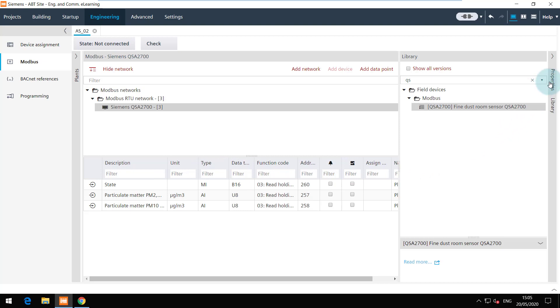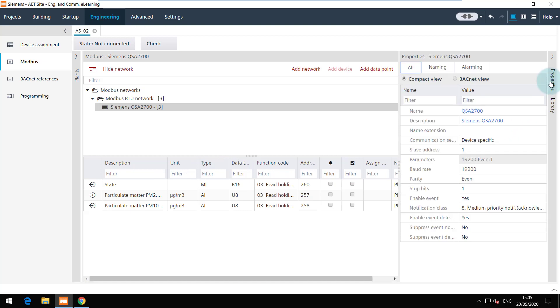In the properties of this device you can see that the communication settings are set to device specific which means it is not inheriting from the network. The slave address is 1 and the baud rate is different than the network we added.